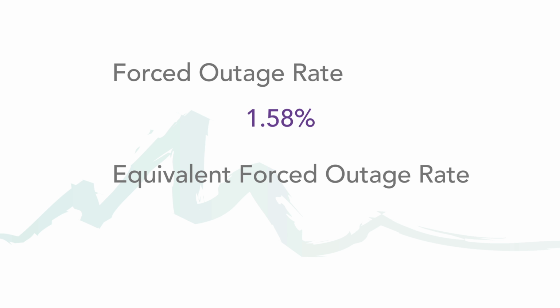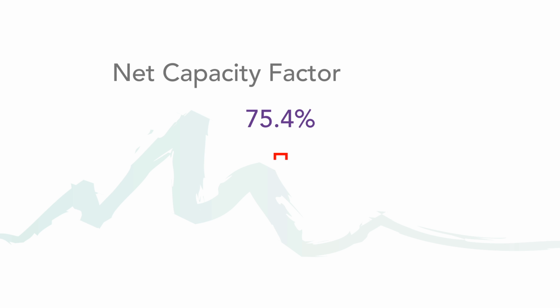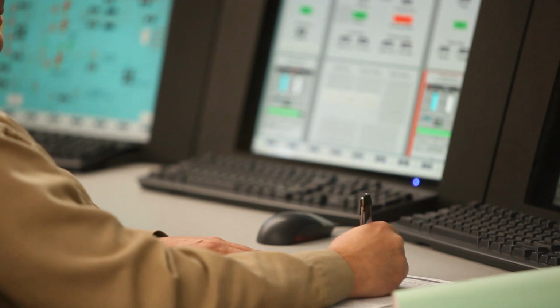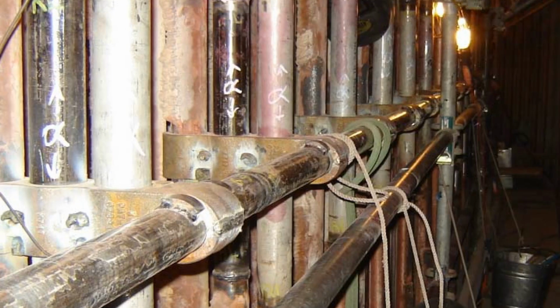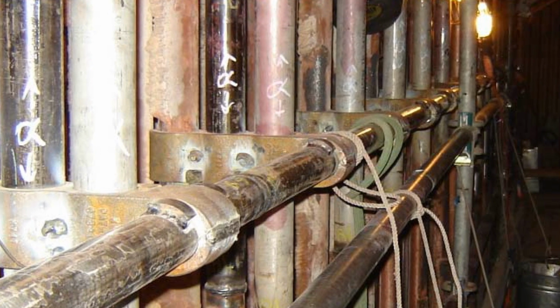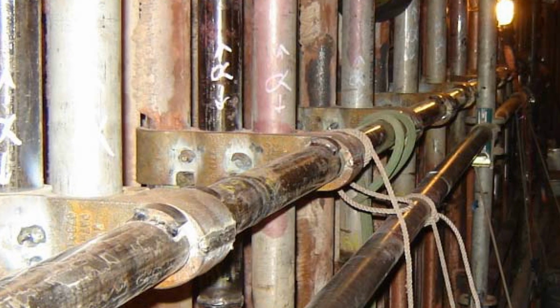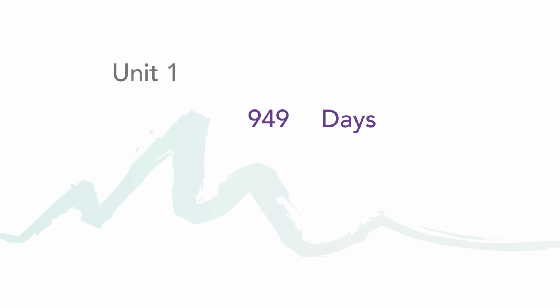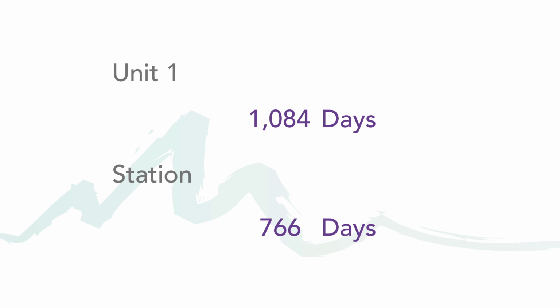Availability and equivalent availability are 89.9% and 89.3%, which compares to a 10-year average of 91.2% and 90.4%. Forced outage rate and equivalent forced outage rate are 1.58% and 2.11%. Net capacity factor is 75.4%, down as a result of low net output factor. The Intermountain Generating Station completed 2 years without a boiler tube failure on September 10, 2013. The boiler tube failure reduction program is reaping benefits, as Unit 1 has gone 1,084 calendar days, its second longest run in unit history, and the station is also in its second longest run in unit history, having gone 766 calendar days without a tube leak.